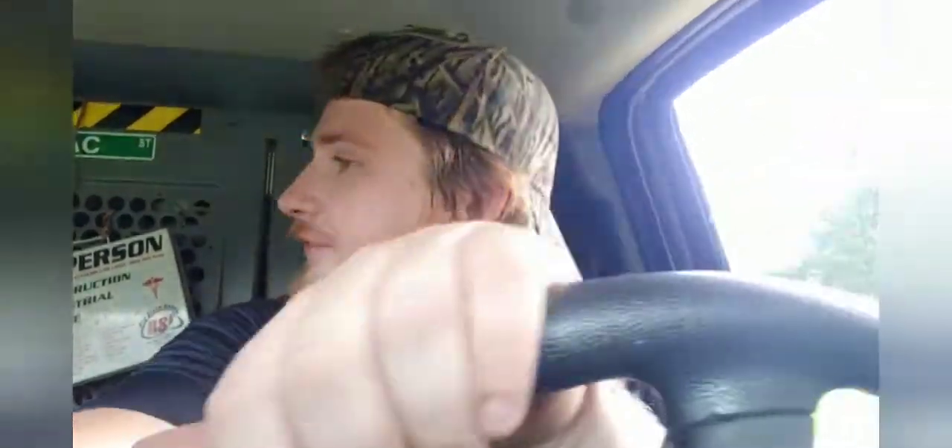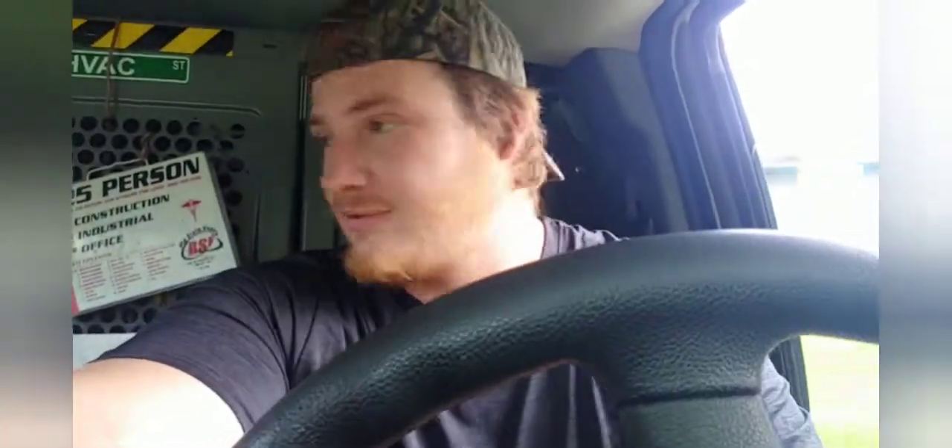Like I said, it's a great day in the life of an HVAC technician. Another one done — got the goods, got the details, it's working good. I hate those little IR thermometers — it's an estimate. His returns were literally twelve to thirteen feet up. I mean, come on, you really think that's going to be accurate? The supplies are way up in there too. The only way I got accuracy was because I put the probe right in the return and right in the supply, as close as I could to the unit. But yeah, it's doing alright. Hopefully the buyers can get another ten years or so out of it, maybe a little bit longer.